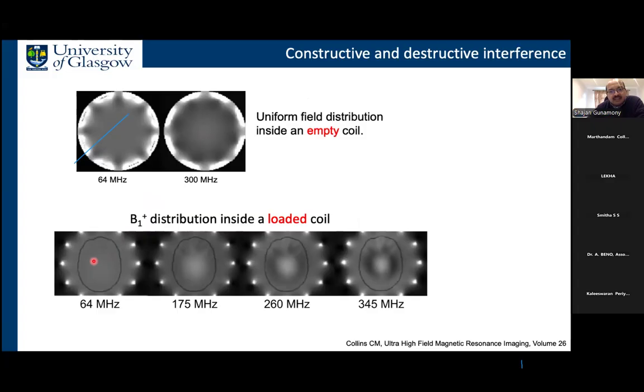And now you can see these bright dots. These are the current carrying elements of the coil. And the center of this coil is at equal distance from each of these current carrying elements. So what happens is that you have constructive interference, because all the phases add, they're all in equal phase because the center is at equal distance. So it constructively interferes, and at about quarter wavelength away from the center, you will see destructive interference. So that is the reason for the center brightening and this darker periphery.